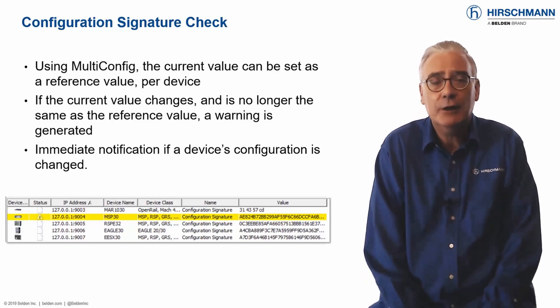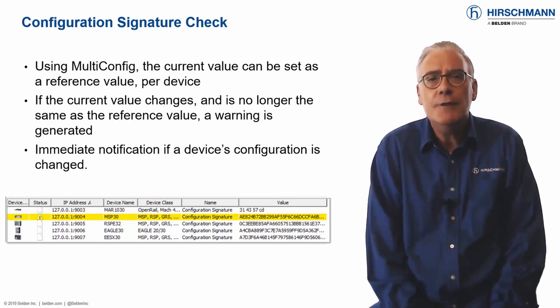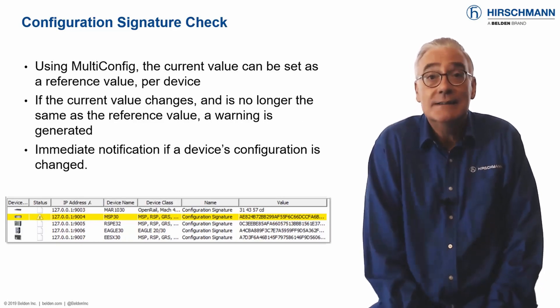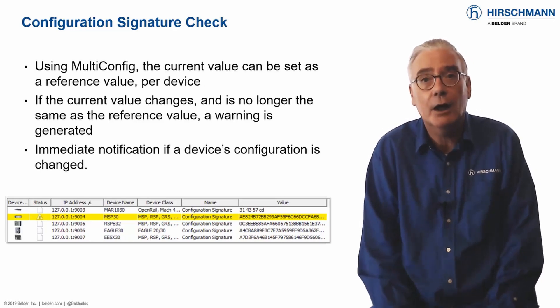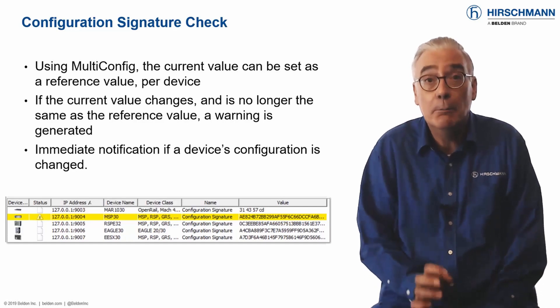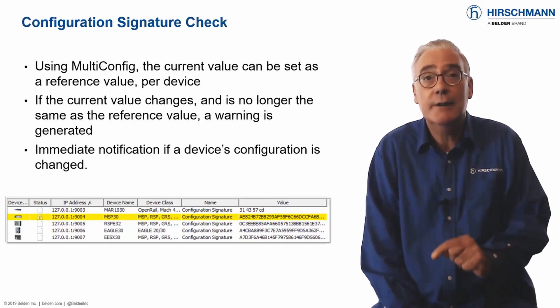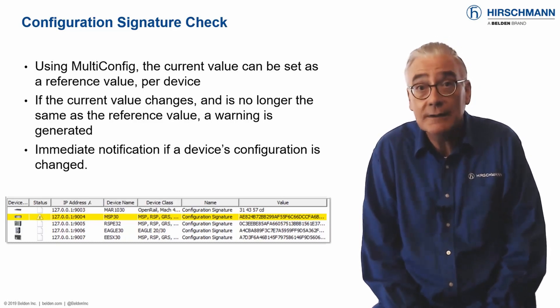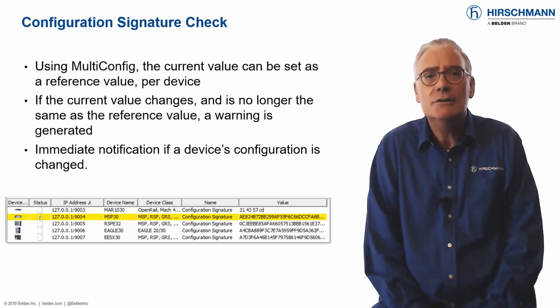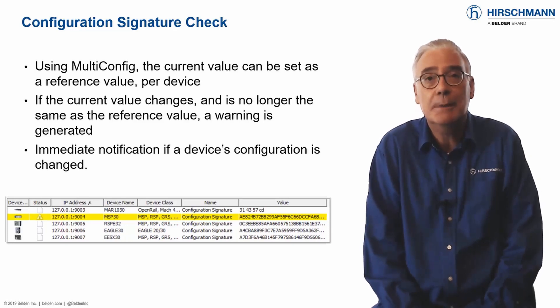Each switch has a configuration checksum known as a signature. If the configuration changes, the signature will change and Industrial HiVision will generate an alarm. Even better, if the configuration is reverted to the previous value, a third signature will be generated — not the original signature. So you can prove that a configuration was changed, even if the change has been reverted.